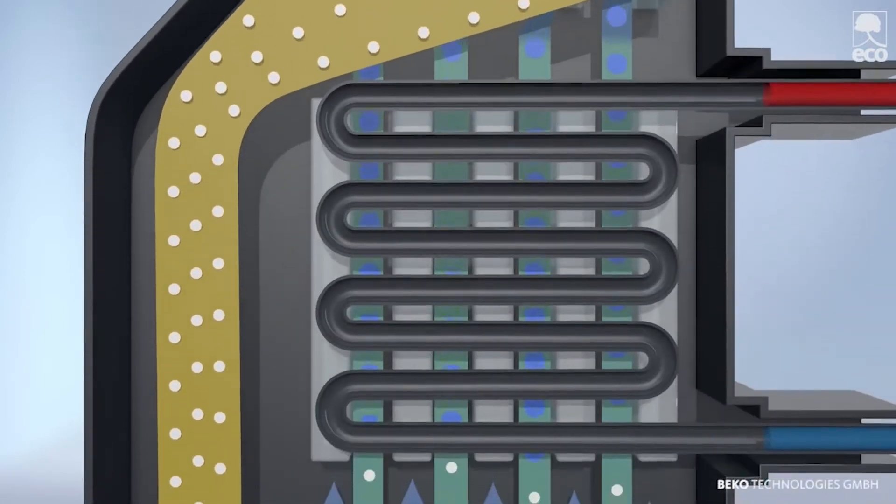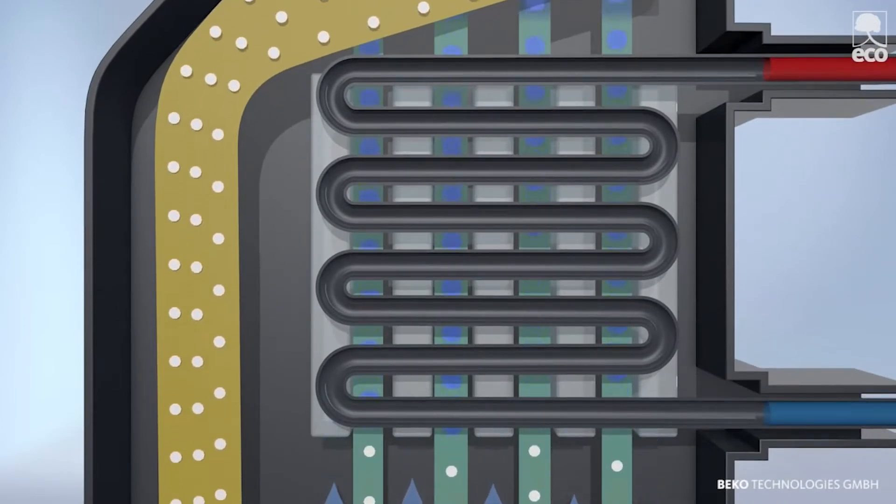It then flows through the actual cooler in which it is continuously cooled down to approximately 3 degrees Celsius. The cold temperature reduces the compressed air's ability to absorb water.